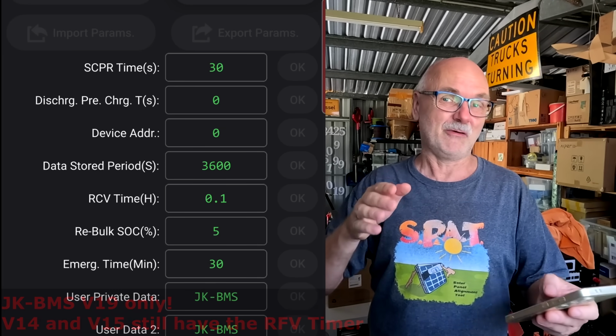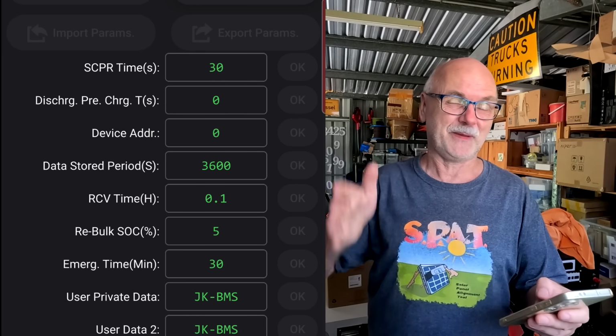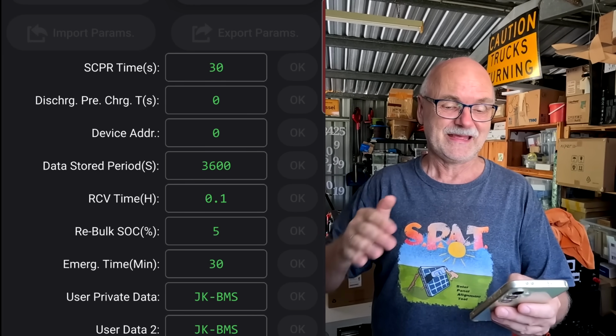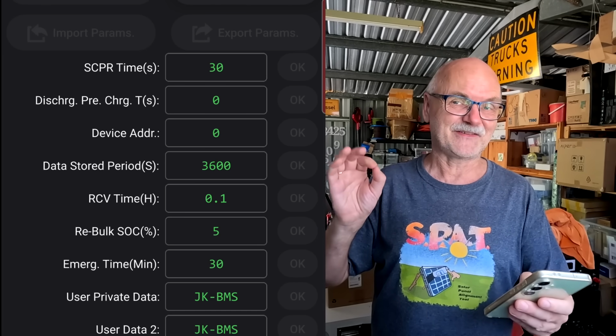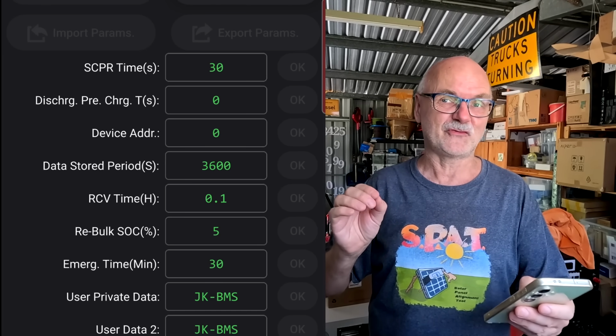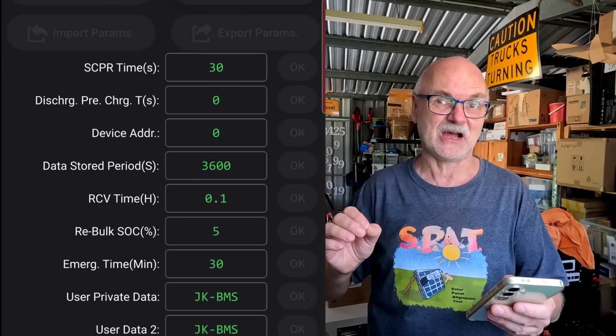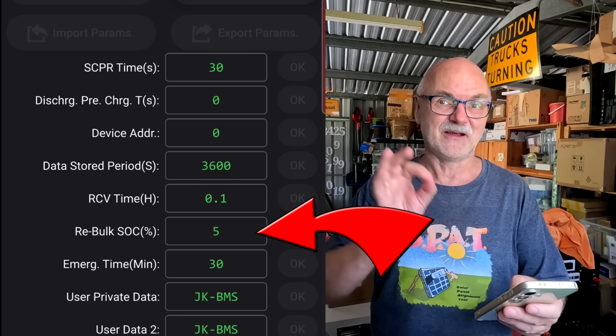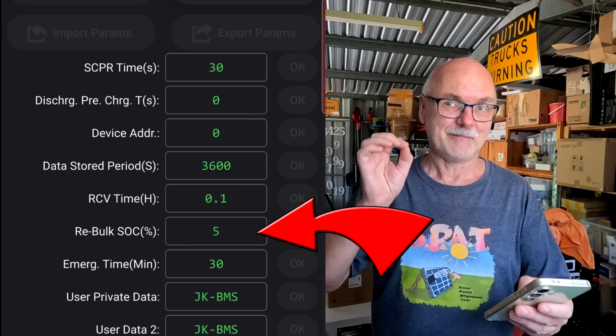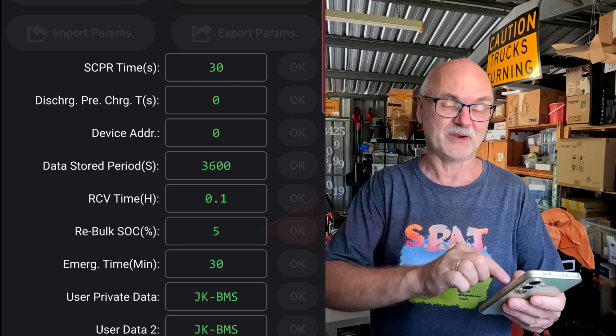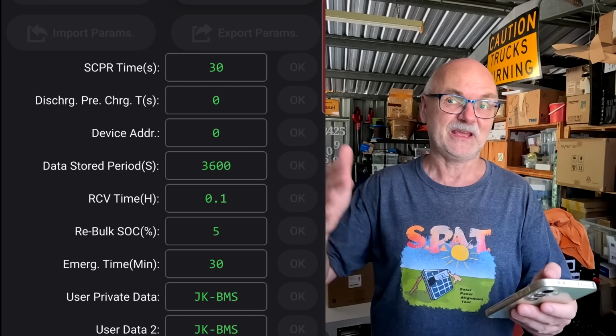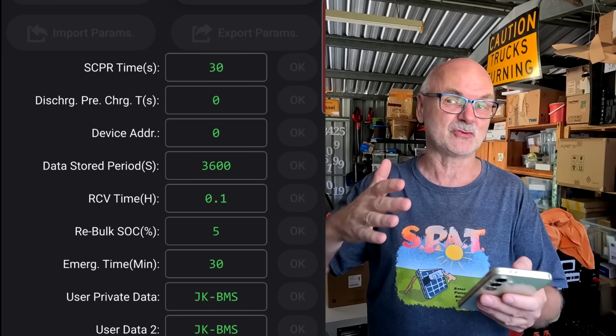This means now, after the absorption time, we go back to 53.6 volts, and then we stay there until the battery goes down to 95% state of charge. Yeah, this is what we have set here, so it's 100% minus 5%, or whatever you have set. If you set 10%, it will wait until the battery is discharged to 90%.